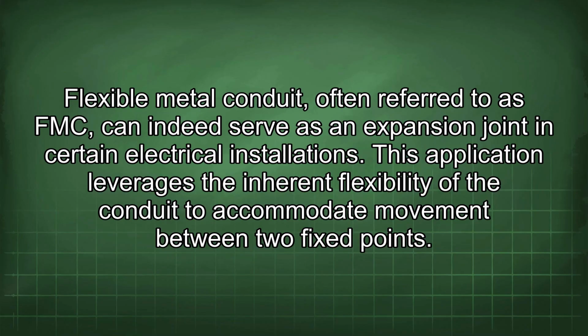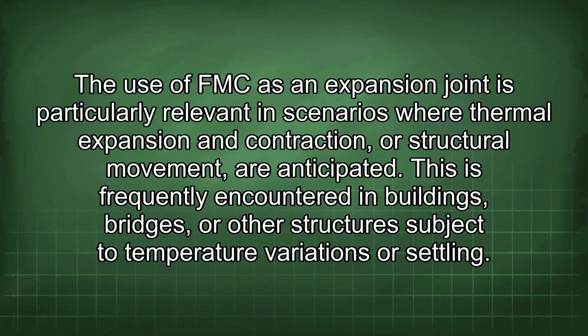Flexible metal conduit, often referred to as FMC, can indeed serve as an expansion joint in certain electrical installations. This application leverages the inherent flexibility of the conduit to accommodate movement between two fixed points. The use of FMC as an expansion joint is particularly relevant in scenarios where thermal expansion and contraction, or structural movement, are anticipated. This is frequently encountered in buildings, bridges, or other structures subject to temperature variations or settling.